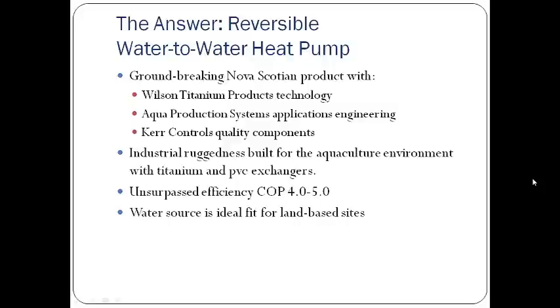And having the aquaculture environment in mind, this heat pump was built to last, built with industrial grade materials and methods. The wetted portions that come in contact with the aquaculture water in and out are built with titanium and PVC, so no corrosion is going to happen. The electrical portions are all built to withstand the environment as well, and the compressors are often reciprocating and more durable and selected for their quality as well. So the unsurpassed efficiency, these are numbers actually measured on Wilson Titanium units that were installed on a federal site.